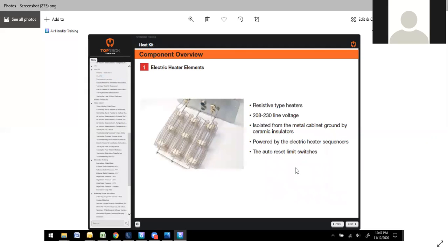These are resistive type heaters. 208, 230 line voltage. They are isolated. They will not touch. They can break eventually if you get them hot enough over a period of time. Extremely low airflow will cause that, but you'll probably get the call beforehand with poor heat.